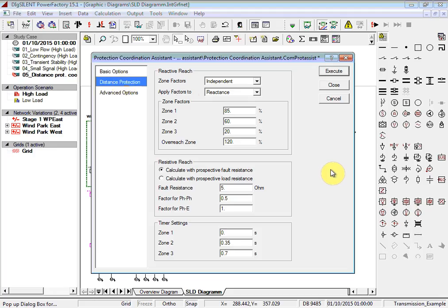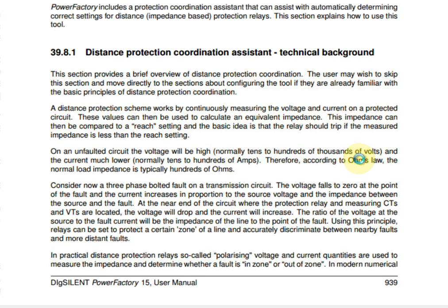On this page, we define the rules which will be used to calculate the reach settings of the distance relays. 3 different calculation methods have been incorporated into the tool for calculating reach settings. You can find descriptions of these calculation methods in the user manual. You can easily access the user manual by pressing the F1 key. If the Coordination Assistant has already been opened, then the user manual should jump to the appropriate part of the manual. Let's take a look at the equations which govern the settings rules for the different calculation methods.